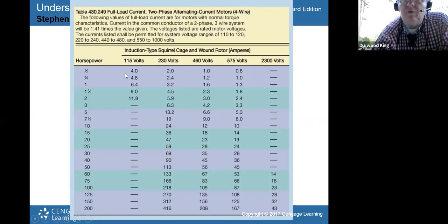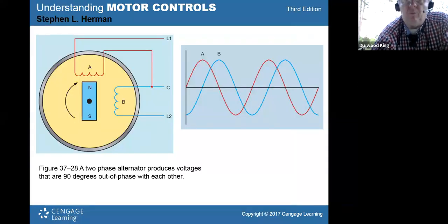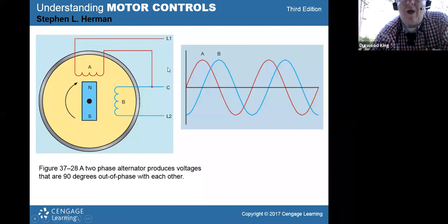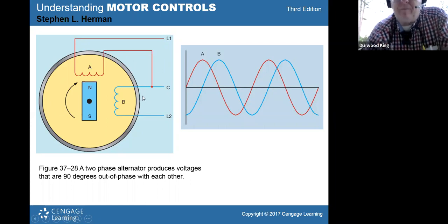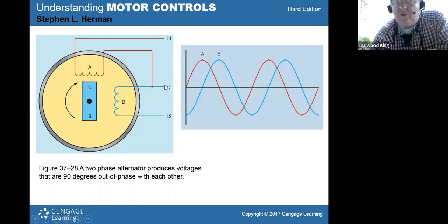I don't know if y'all have any 2-phase motors or not, but the diagram for one of them, just so you can see, would be that. You have a hot wire here and a hot wire there. You've got 2 legs, and then those 2 ends of the windings in the motor are wired together to a common. So that would be a neutral leg right there. It's a 3-wire feeding it, but it's 4 wires in the motor. That's a 2-phase motor. It runs on 2 phases plus a neutral.